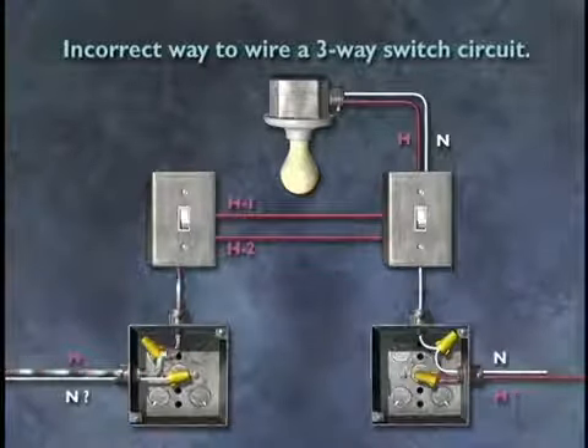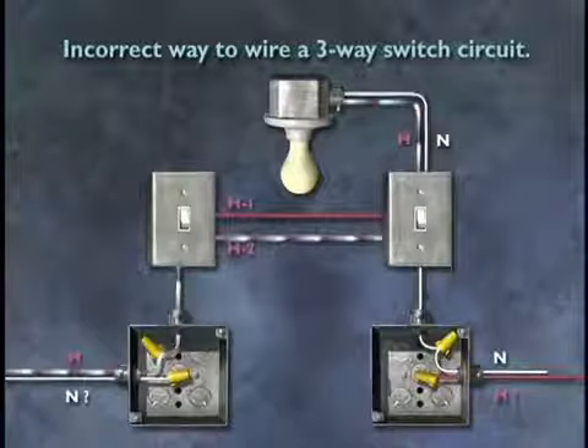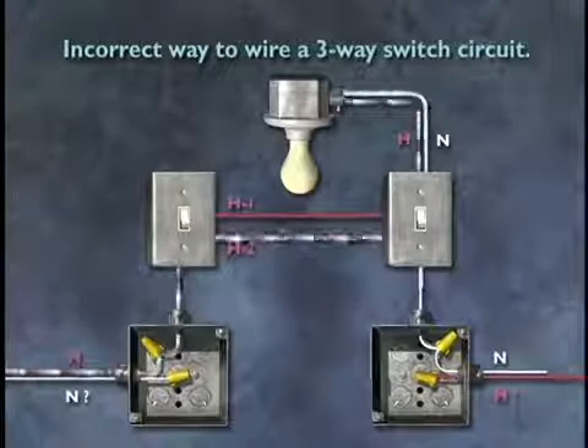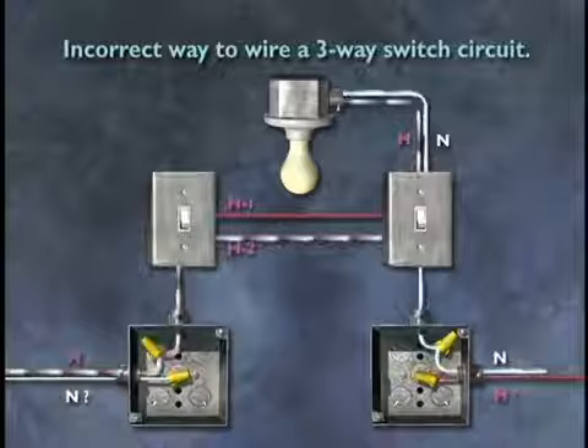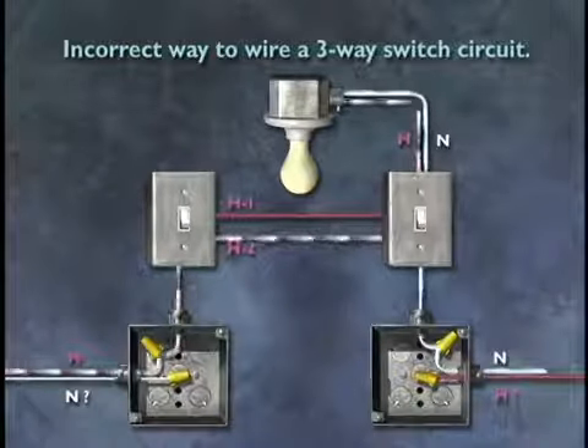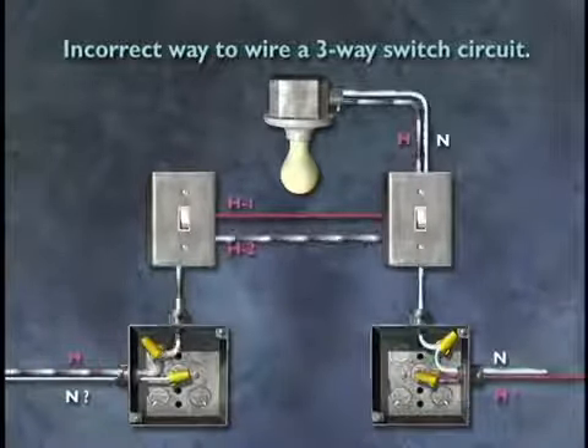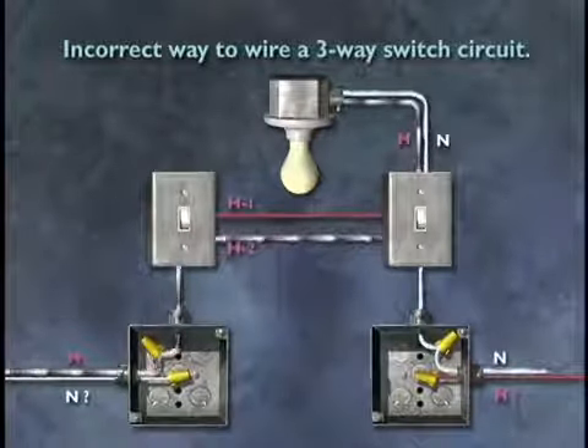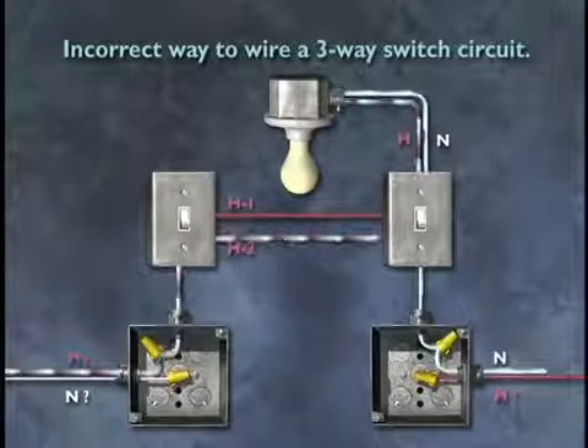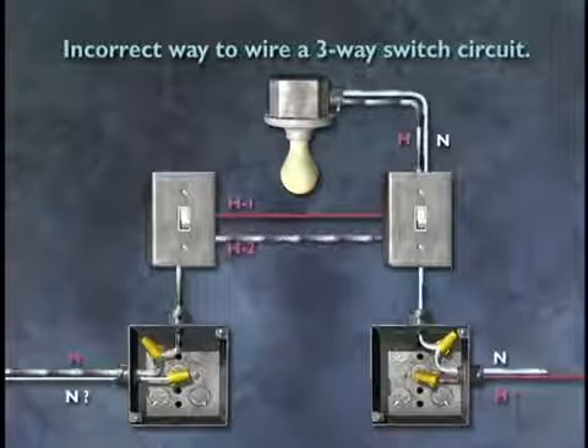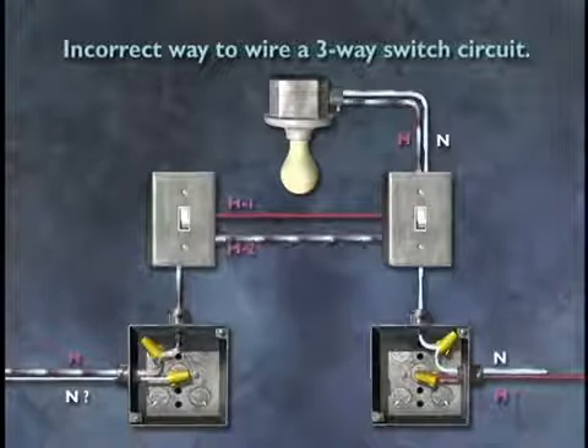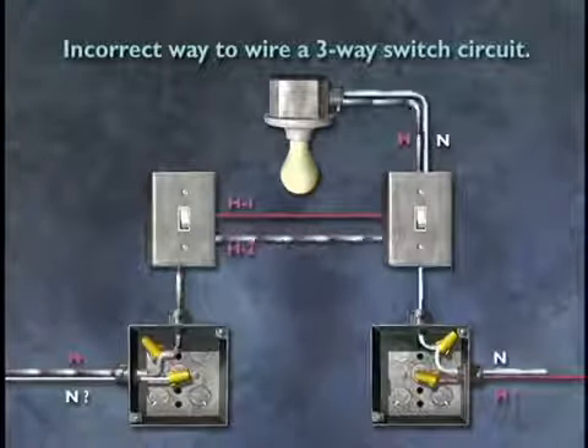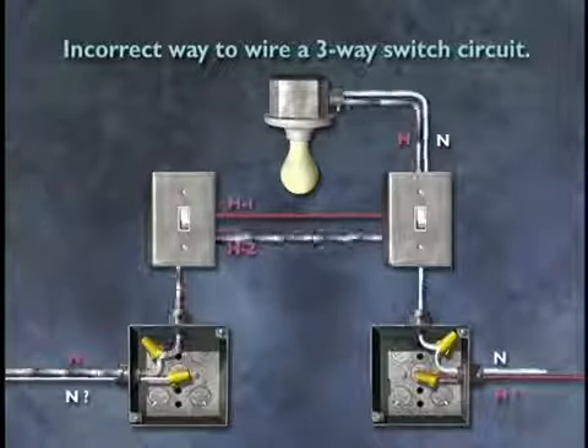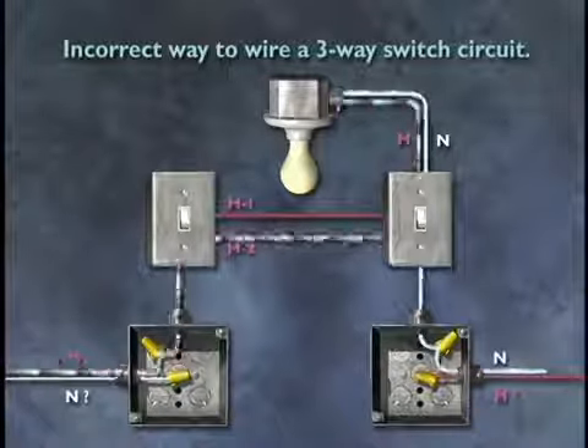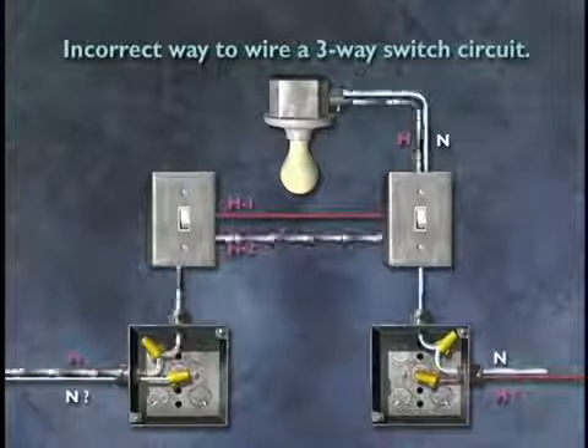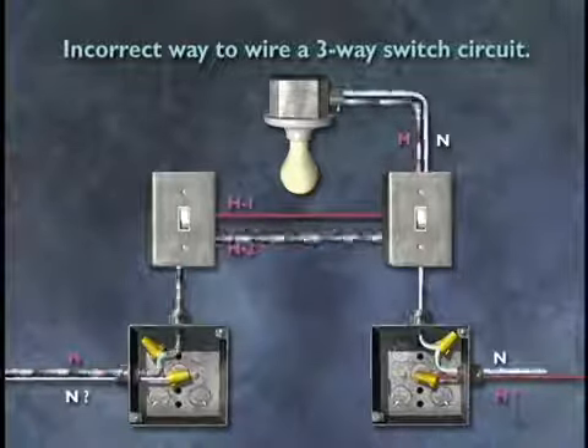Now let's look at one of the many ways to miswire a three-way circuit. The installer uses only the hot to run to switch 1. This enables him to use a two-conductor traveler to switch 2, since he picks up a neutral from a circuit near switch 2. The result is net current and high magnetic fields from every part of these circuits except the run to the light. This installation violates NEC 300-3B. There is no way to get by with using a two-conductor traveler.